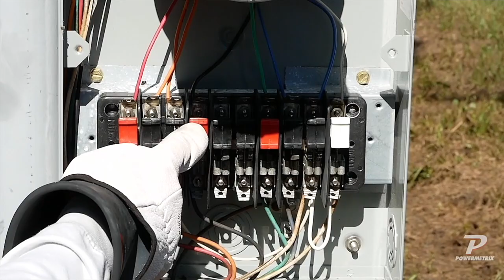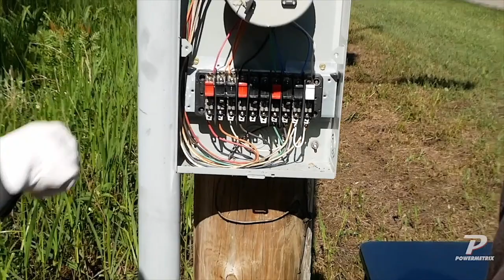In this case we've got tabs with holes in them, so you could hook in with alligator clips, grabbing right into those holes at the ends. There are locking teeth that will lock onto the end and hold it in place securely, and Jonathan's going to demonstrate that in a second. Alternatively, you could get on the blades and coin that surface a bit to make contact there. It's your choice in the field, either the blade or the tab end with the holes, which makes it easier. You can use alligator clips or get on the blades, either works, but remember that with the older, short, thick, stubby test switches, it's hard to make good contact with alligator clips, especially if the little metal ends are broken off, so in those cases you'll want to get on the blades instead.